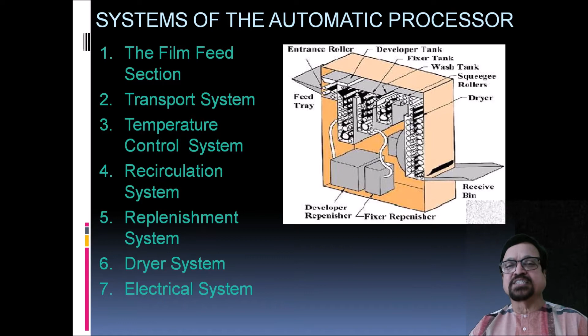Now the film feed section, as the name implies, the film is fed into the processor so that the cycle of events listed below is initiated. The driver motor energizes, that is to turn the rollers, and the safe light above the feed area is extinguished. Now developer and fixer replenisher are pumped into the tanks so the level is maintained. The dryer is heated and energized. Wash water starts flowing, then the film signal delay timer is activated.